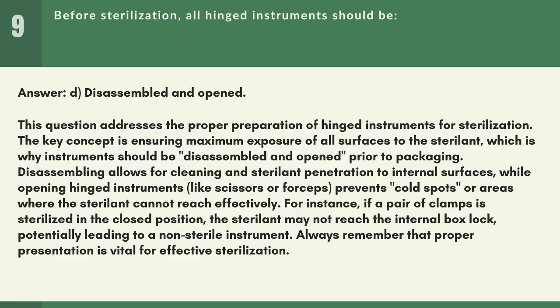Disassembling allows for cleaning and sterilant penetration to internal surfaces, while opening hinged instruments, like scissors or forceps, prevents cold spots or areas where the sterilant cannot reach effectively. For instance, if a pair of clamps is sterilized in the closed position, the sterilant may not reach the internal box lock, potentially leading to a non-sterile instrument. Always remember that proper presentation is vital for effective sterilization.